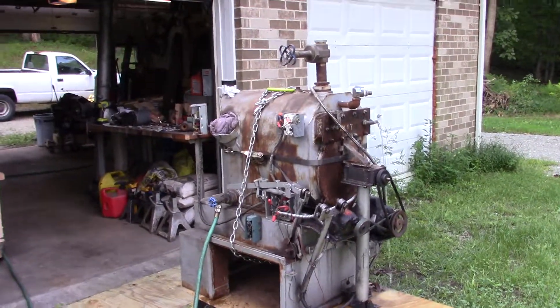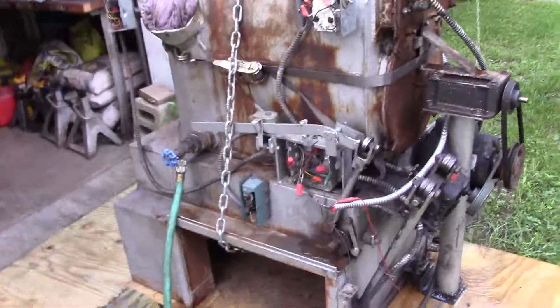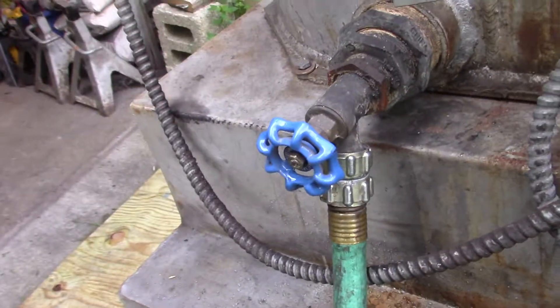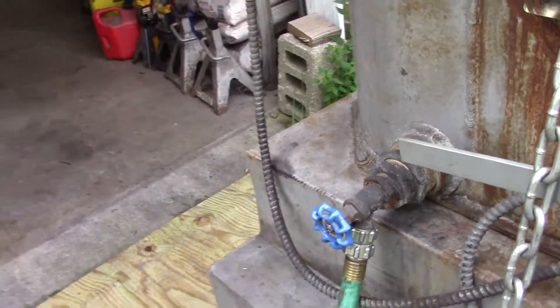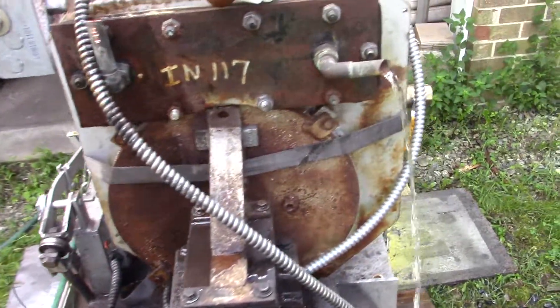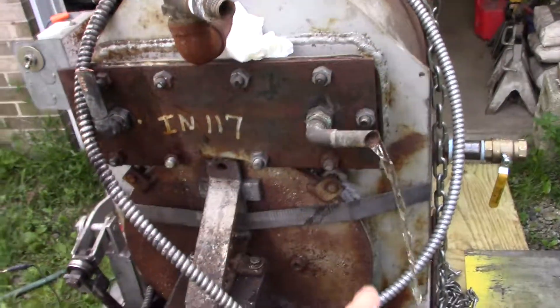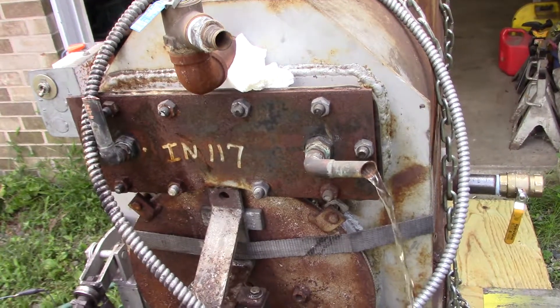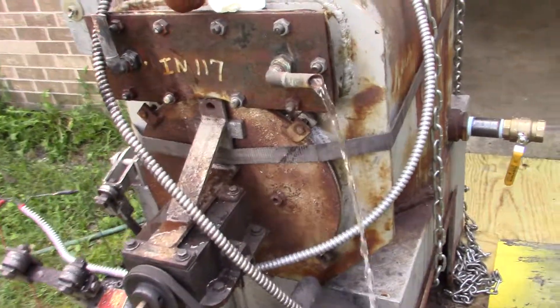We're doing the pressure test on this 1959 Axeman-Anderson 130m. The first thing that started leaking was the boiler drain, so we replaced that — not a big deal. But what's more of a big deal is the domestic coil.